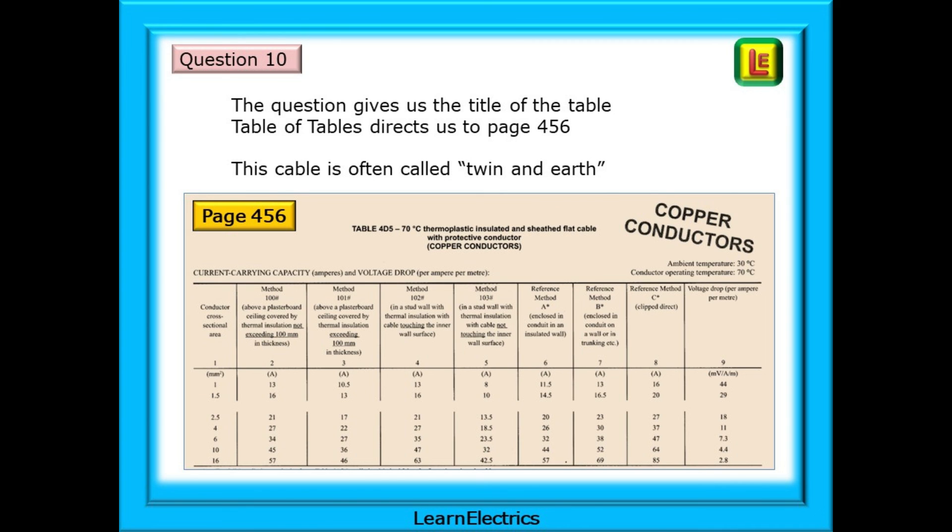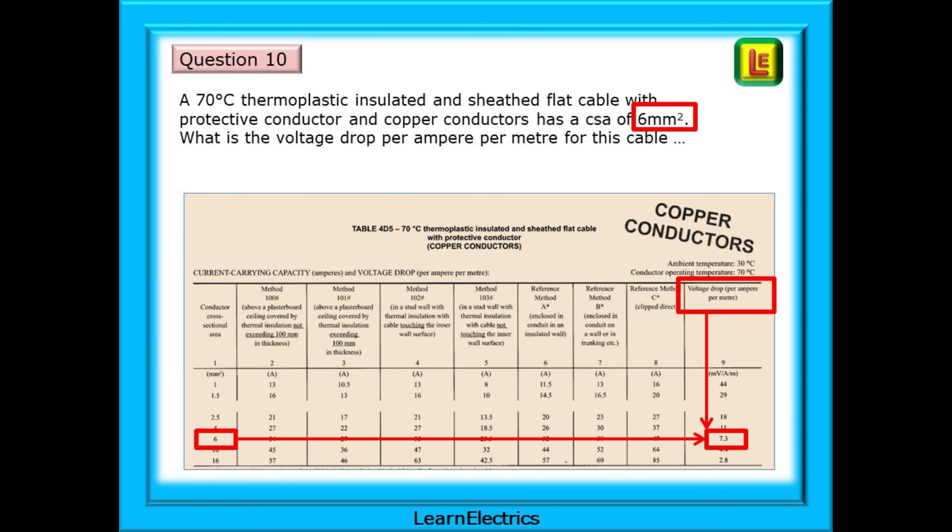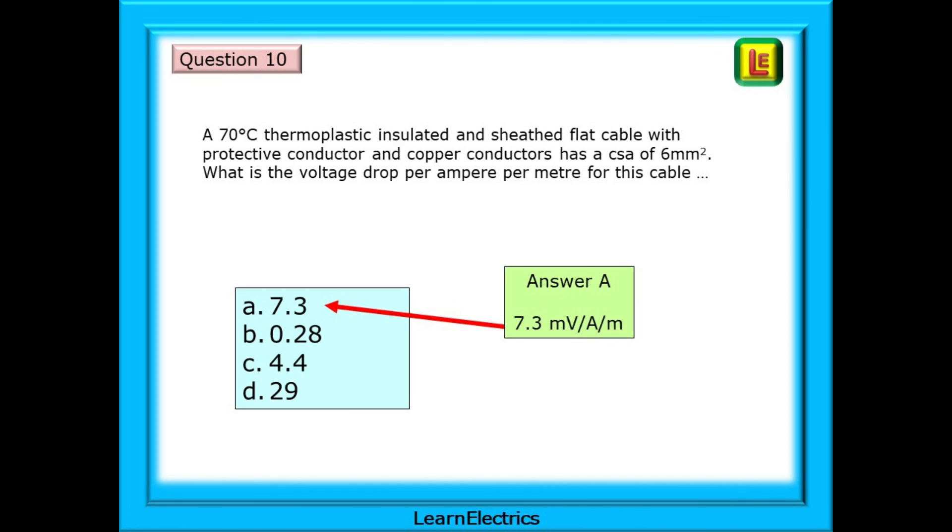The first line of the question gives us the title of the table. We can find this on page 575 of Table of Tables. It is Table 4D5 and we are sent to page 456. This sheathed flat cable with a protective conductor is what we know as Twin and Earth cable. Remember this one. You will not find a table called Twin and Earth. This is it. Follow the question. All it's asking is if the live conductor size is 6 square millimetres then what is the voltage drop per ampere per metre? Don't calculate anything. Just look at the table. Find 6 on the left hand side. Trace along the row to the right hand side and read off the answer. 7.3. Our answer is A. 7.3 millivolts per ampere per metre. That's it. That's all that is asked. And that was the last question on Table of Tables.